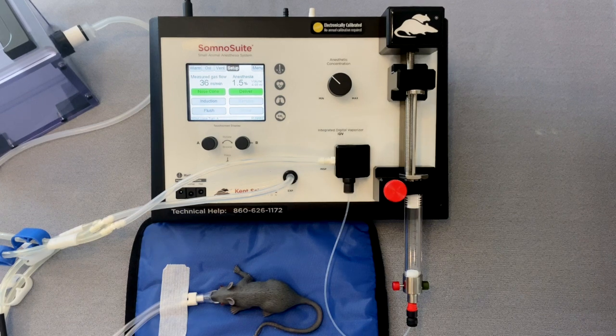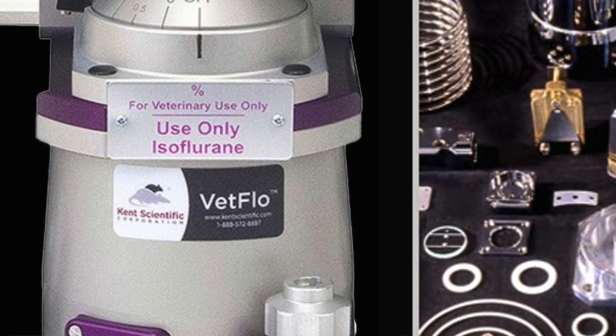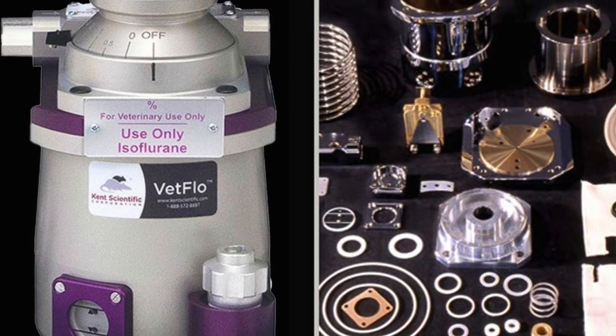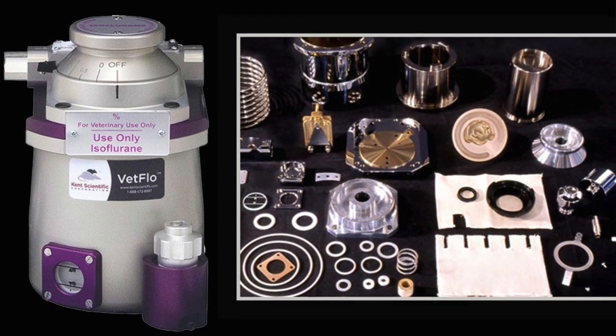Did you know the SomnoSuite low flow electronic vaporizer does not require any annual calibration or recertification? The SomnoSuite system uses a different technology for anesthesia delivery than traditional vaporizers. Traditional anesthetic systems rely on passive vaporization and moving mechanical parts to control the vaporization of the anesthetic. The physical nature of these moving parts requires annual calibration to maintain accuracy of delivery of the anesthetic agent.